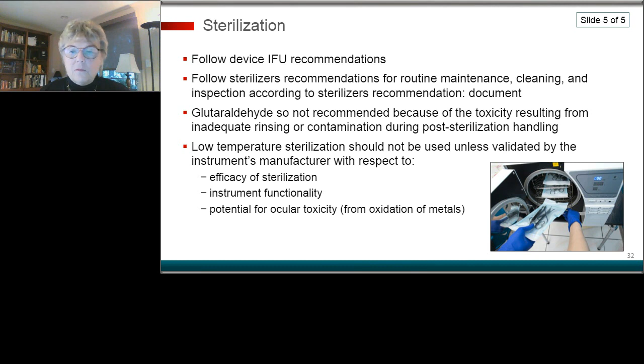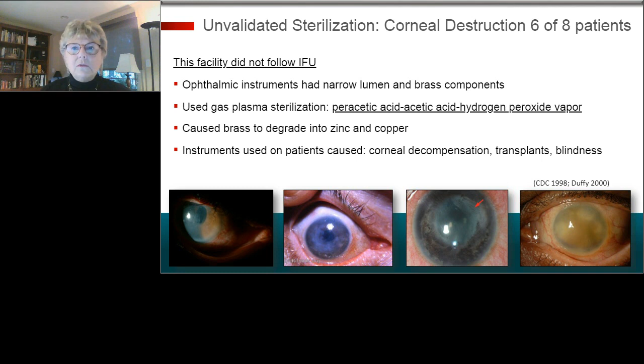Ophthalmic instruments had narrow lumen and brass components in this particular instance, but they decided to go ahead and use the cold sterilization. It seemed logical, it was faster, and it seemed like it would be a good idea. They used the gas plasma sterilization. It caused the brass to degrade into copper and zinc. And the instruments were used in the patient. They caused corneal decompensation, transplants, and blindness. A whole number of them, 6 of 8 individuals in this particular facility.